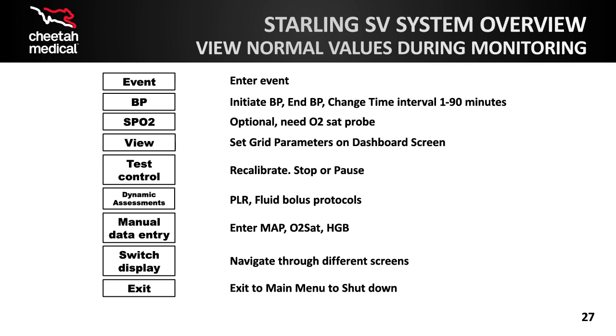View may change grid parameters on the dashboard screen. Test controls initiate calibration or pause the monitor. Protocols are for passive leg raise or fluid bolus, and manual data entry is to enter MAP, SpO2, or hemoglobin. When SpO2 and HB are entered, DO2I will be displayed. Switch display to display different screens. Exit to turn the monitor off.